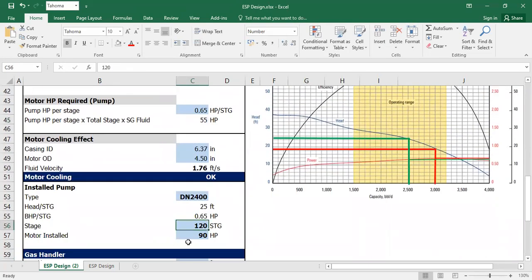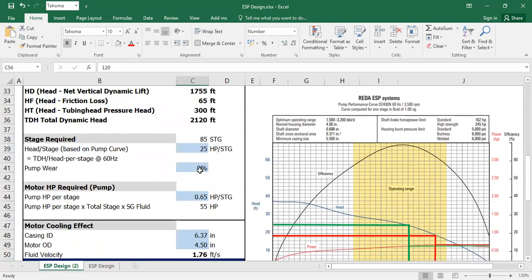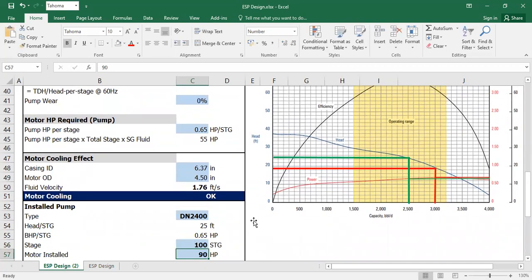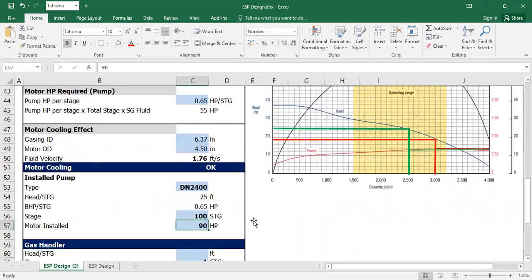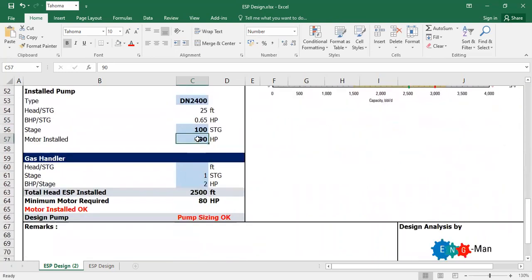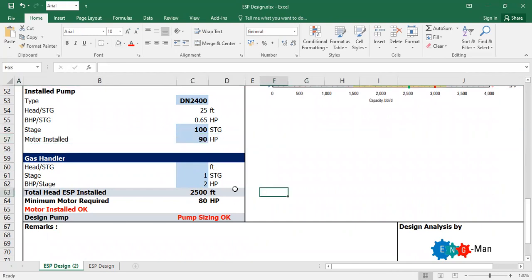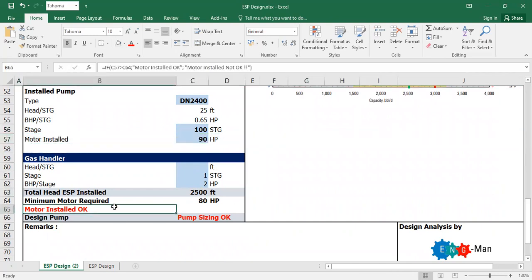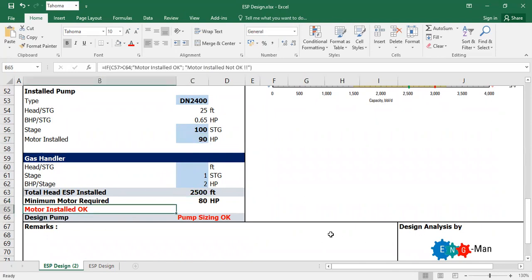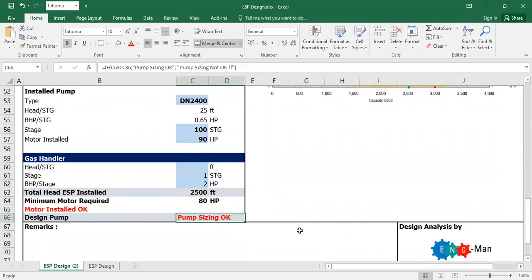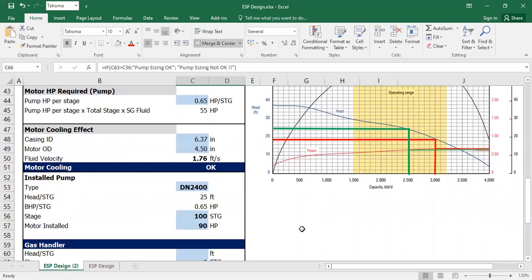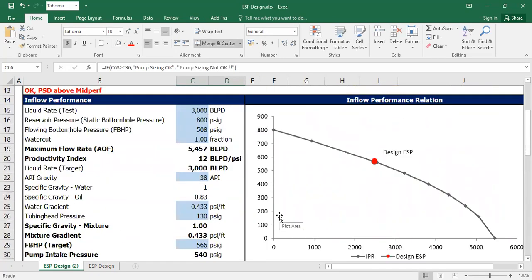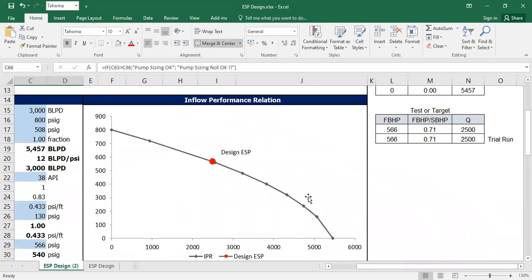So actually I can provide let's say 100 stages instead. Motor installed horsepower 90. Now motor installed okay because minimum required is only 80 horsepower and the available motor is 90 horsepower. Motor installed okay, pump sizing okay. So pump sizing okay if now I lower down my target flow rate to 2500.